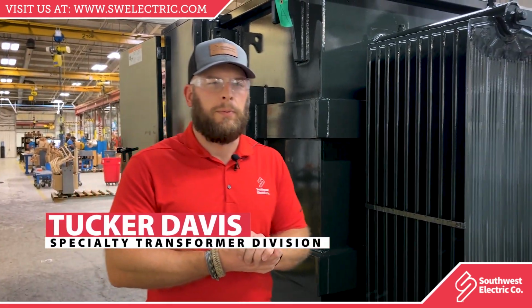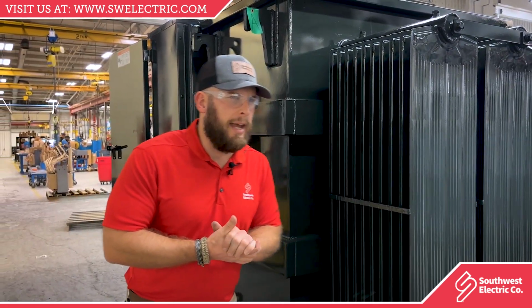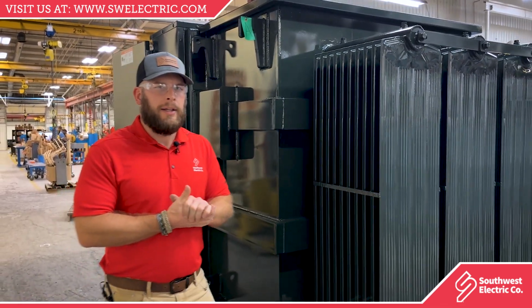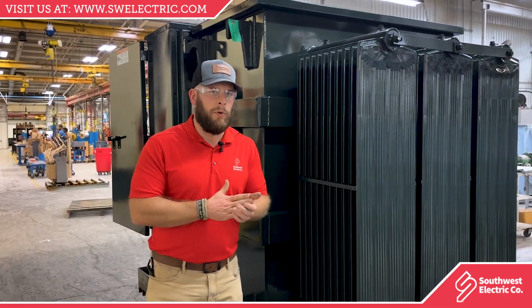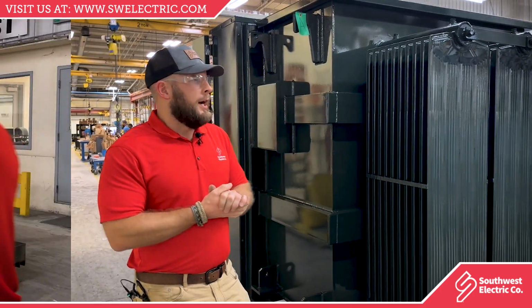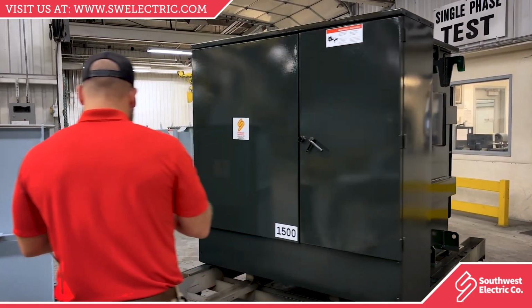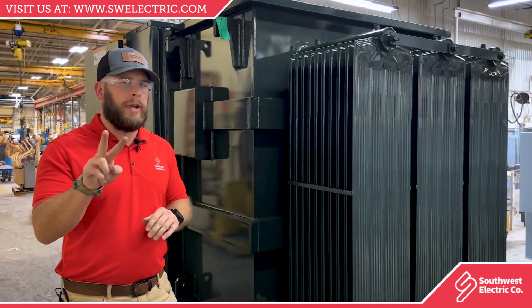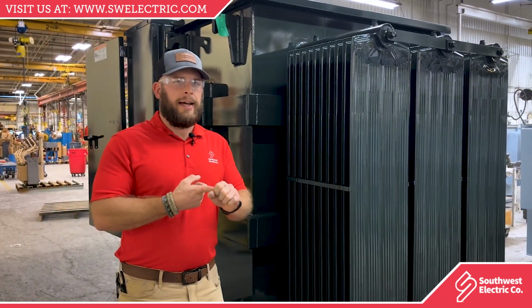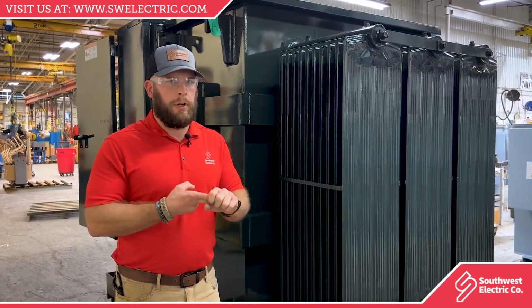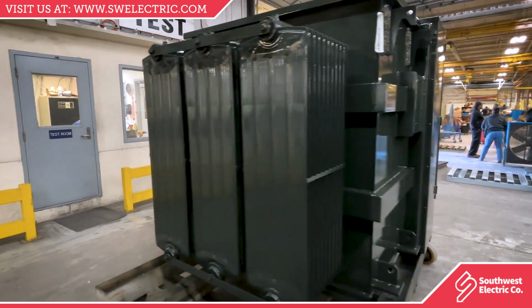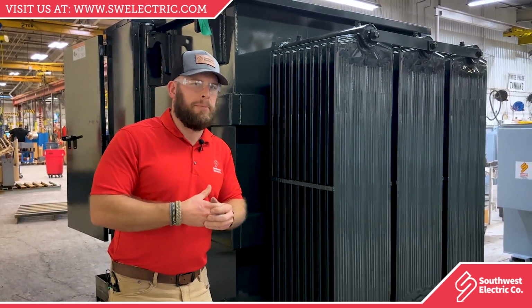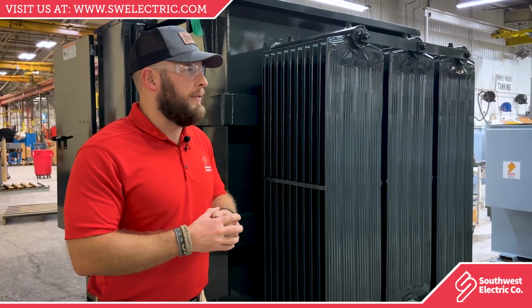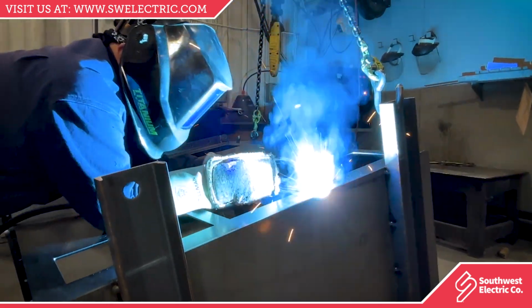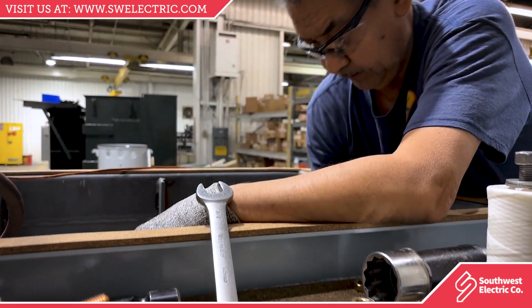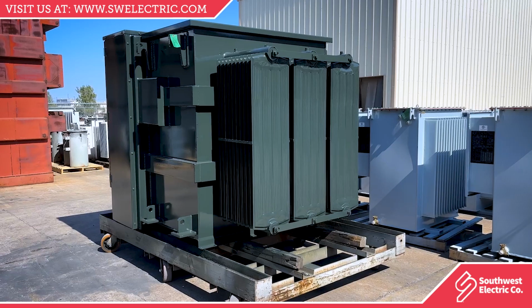I'm with the Specialty Transformer Division of Southwest Electric, and today I'm going to be talking to you about the different types or methods of cooling for transformers. For distribution class transformers, there are two categories. That's going to be a dry type or an oil or liquid immersed. They're exactly as they sound. Dry type is completely dry with no liquid whatsoever in it. Those are not a product that we manufacture. We build the other one, the oil immersed or liquid immersed.